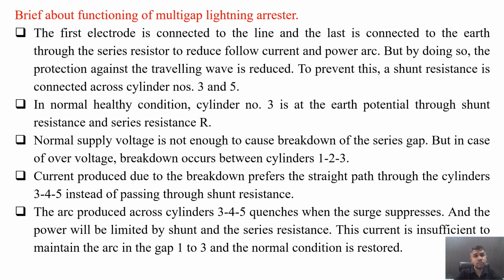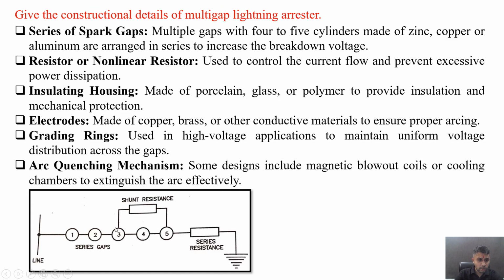So the first electrode is connected to the line and the last is connected to the earth through a series resistor to reduce the follow current and power arc. But by doing so, by connecting the series resistor, the protection against the traveling wave is reduced. To prevent this, a shunt resistor is connected across cylinder number 3 and cylinder number 5, which we have already seen in the previous figures. A shunt resistance is connected across gap 3 and 5 and series resistance is connected like this.